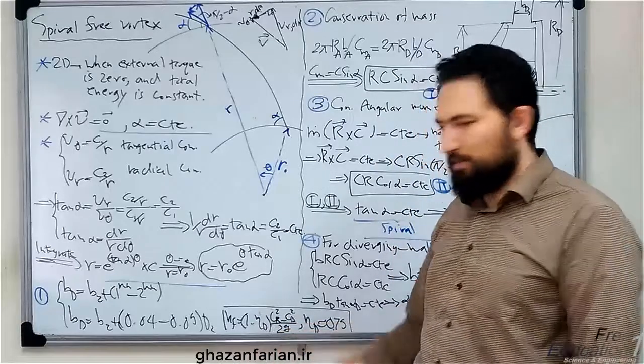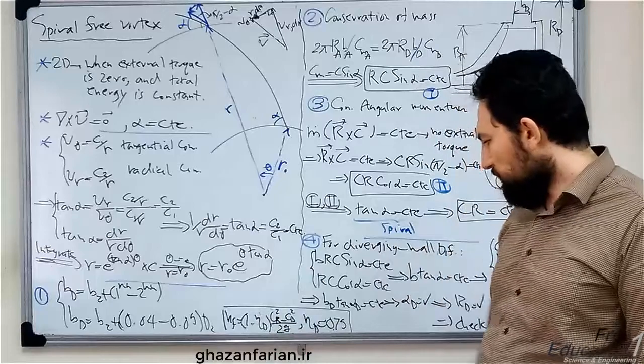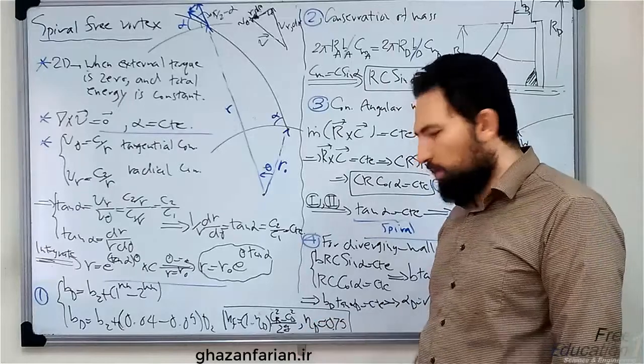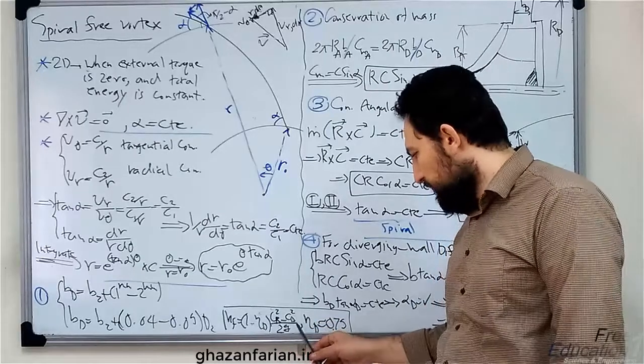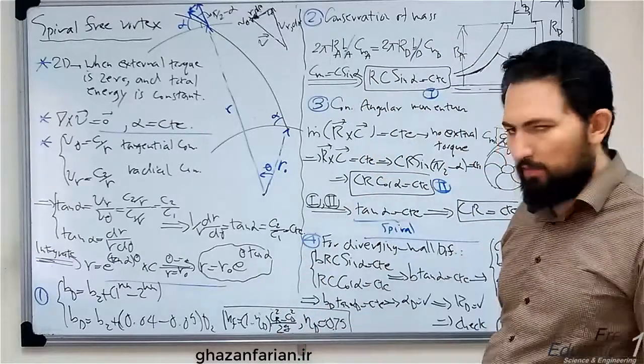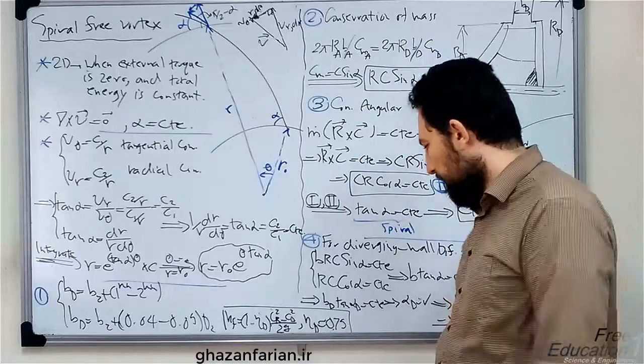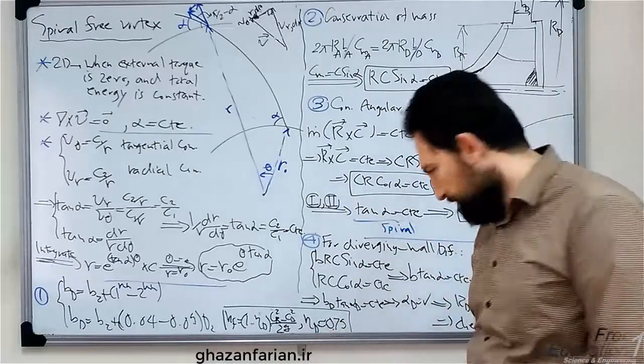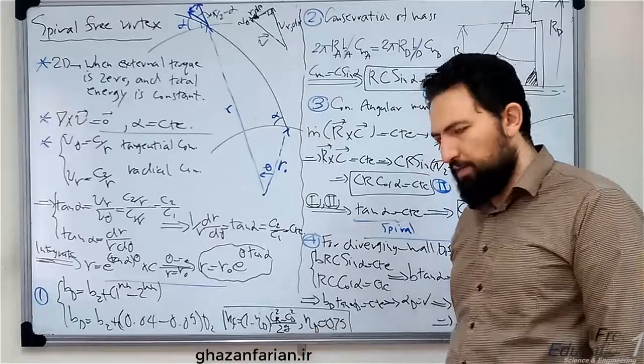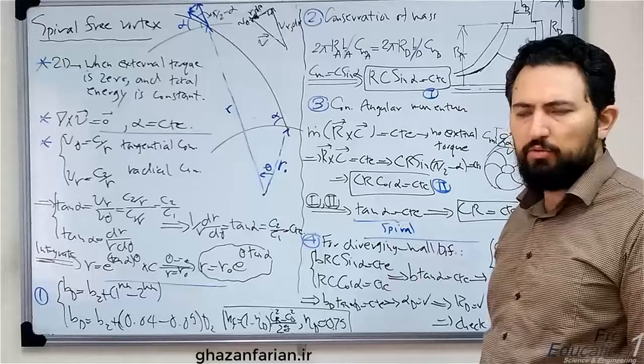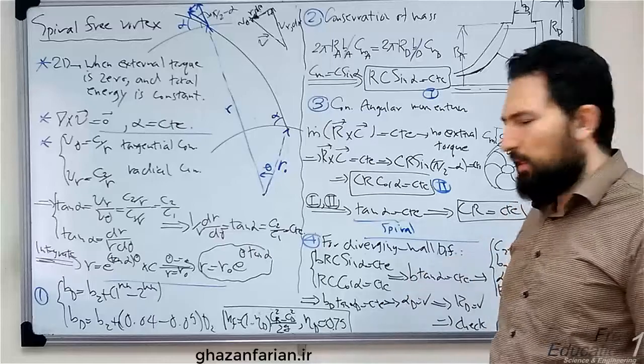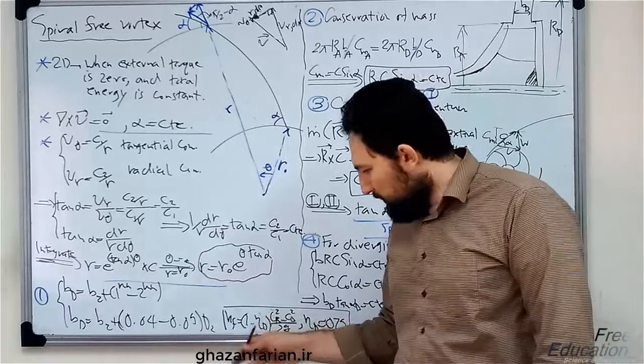Eta sub D is the efficiency of the diffuser. The hydraulic loss equals (1 − η_D) times (C_R² − C_D²) divided by 2g, where C sub R is the velocity at the inlet of the diffuser and C sub D is the velocity at the outlet. Eta sub D in common applications is approximately equal to 3/4, or 75%.